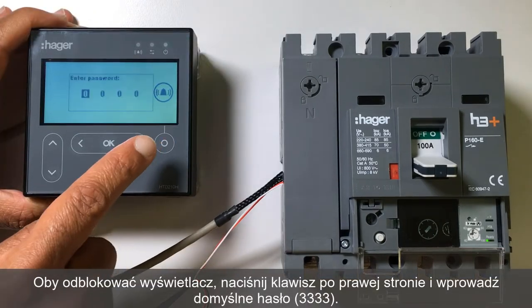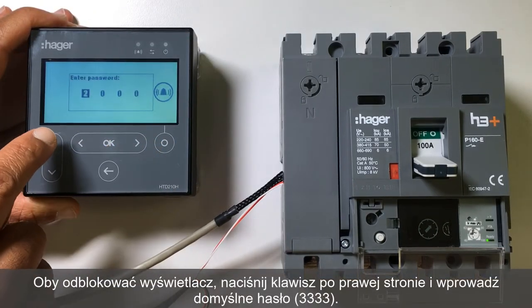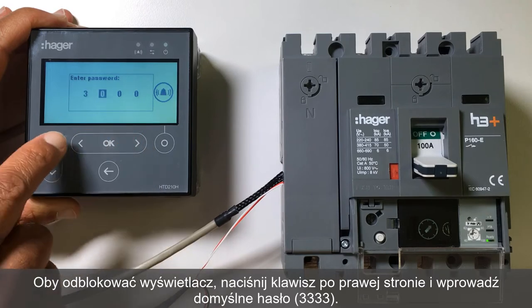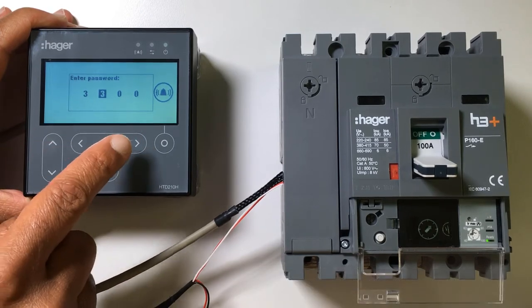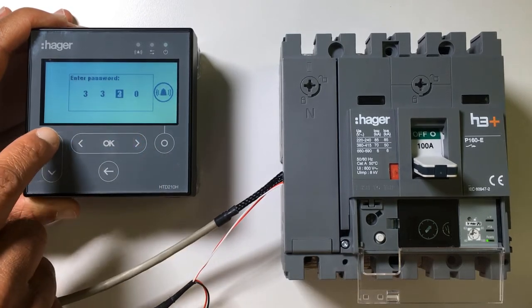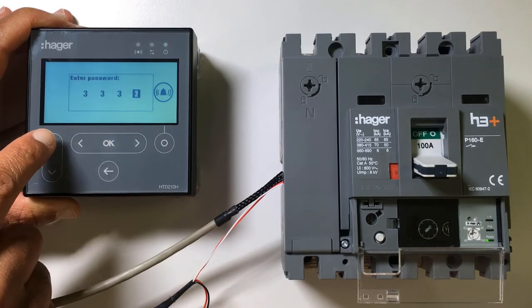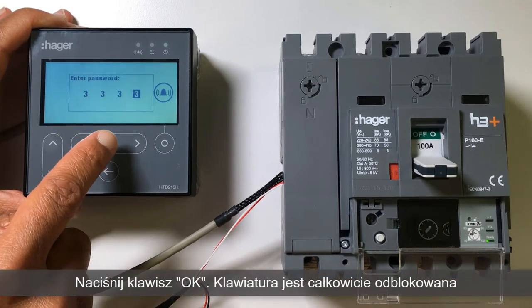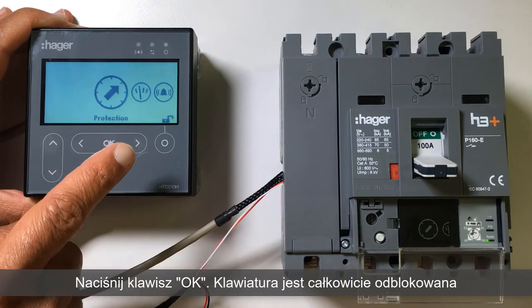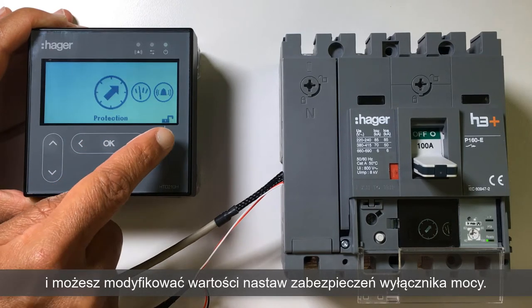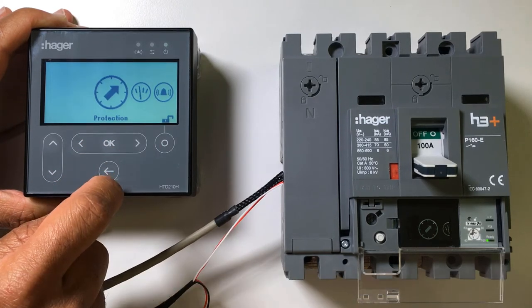To unlock the display, press the right button and enter the default password. Select OK. The padlock is now unlocked and you can modify the circuit breaker protection settings.